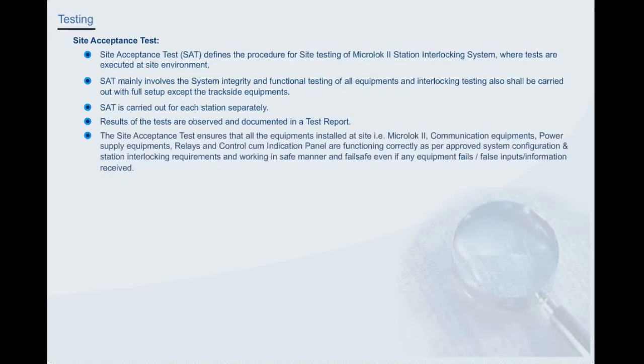The site acceptance test ensures that all equipments installed at site, that is, Microlok II, communication equipments, power supply equipments, relays and control cum indication panel are functioning correctly as per approved system configuration and station interlocking requirements and working in safe manner, and fail safe even if any equipment fails or false inputs or information received. Site acceptance test ensures the overall system safety and error-free system is being delivered to the client.